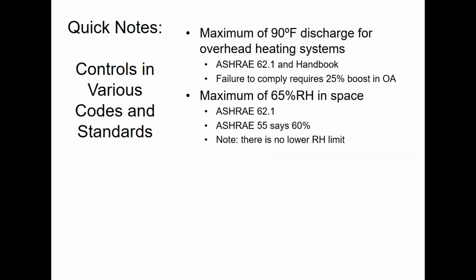ASHRAE 62.1, which is the IAQ standard, also specifies a maximum of 65% relative humidity in the space. ASHRAE 55, which is the thermal comfort standard for humans, specifies 60%. So I end up controlling the cooling system to maintain below 60% because that satisfies both requirements.